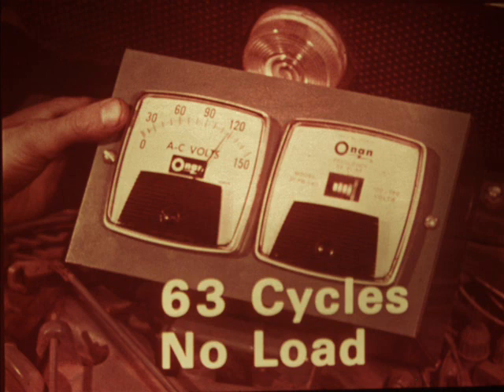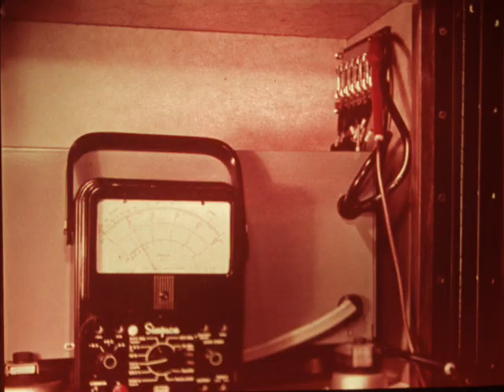Plug a frequency meter into the outlet. If the motor generator doesn't put out 63 cycles at no load, it needs maintenance. So refer to your GMC Motorhome service manual. If you have good power into the converter, but the output voltage isn't up to specifications, replace the converter.